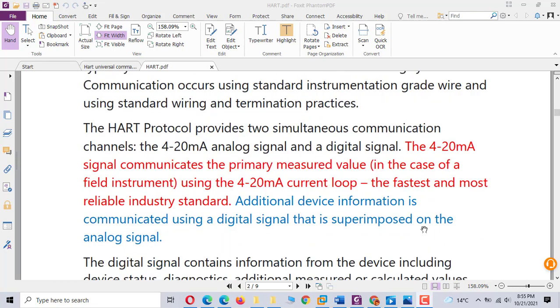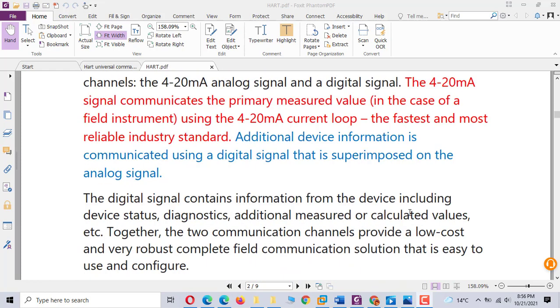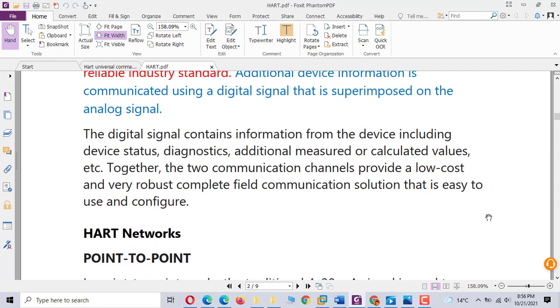So in HART communication, the 4 to 20 mA current is the analog signal, the field side signal, for example temperature, pressure, flow. The digital signal is just for information. The digital signal contains information from the device, including device state, diagnosis, additional measurements, or calculated values. So the two communication channels provide low cost and very robust complete field communication.